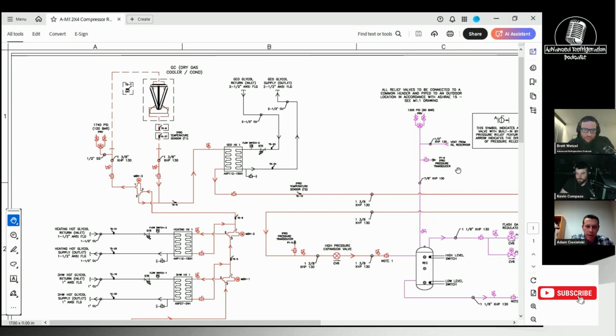I have to work out the rest of the algorithm, but I do see a huge opportunity to improve the controllability across the board. You do have to work out at what point to stop controlling off pressure and release back. And I have some ideas, because eventually, as the ambient warms up, you can still float that set point in pressure units, right? You can still walk it up just as you do with a floating TD. It works fine, but we're going to have to work out how we transition into the transcritical zone. Do we switch back to temperature, or do we just keep the pressure set point low enough below the transition point? That's what we were doing.